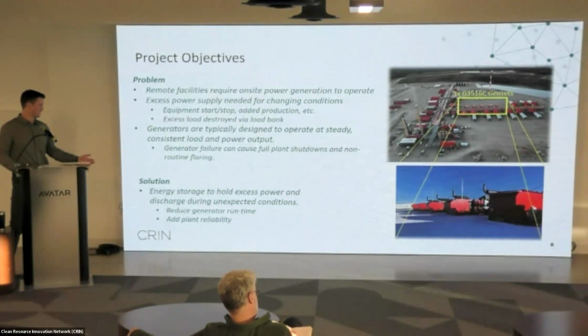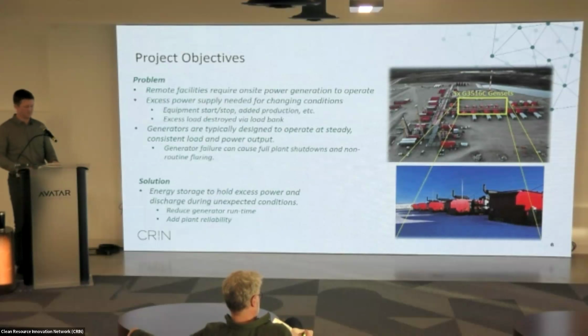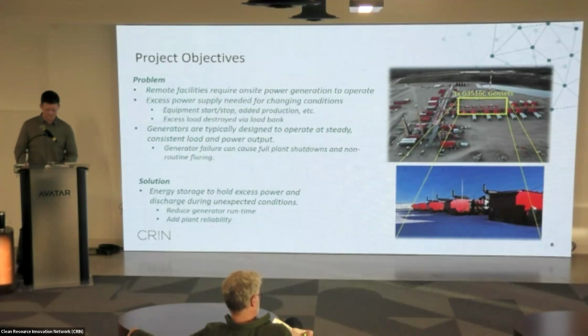The solution we were looking at was a battery within this system. The idea was that we could run fewer generators—instead of running 4, try running 3—and have the reliability to discharge in an event where we lose one of the generators.